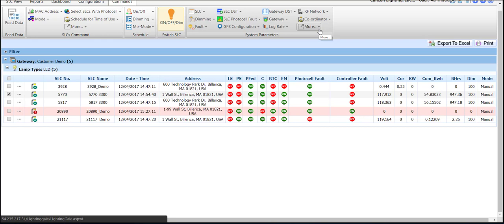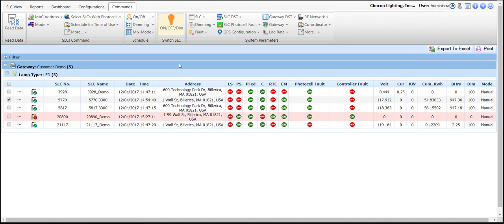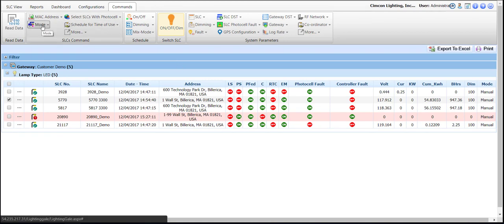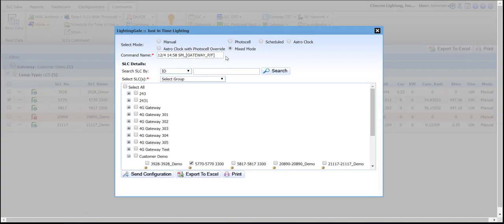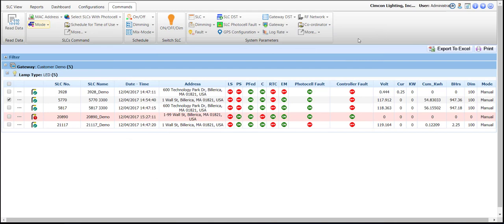Now let's say we have confirmed visually or via the CMS that this SLC is operating as expected and the testing is complete — we will want to revert this SLC back to its previous mode of operation. I will come in here under the Commands tab, then go to Mode Set, and bring it back to mixed mode. I select that, the SLC is selected, and I send configuration. To verify that it has returned to its previous mode of operation, we would want to read data from it to pull the new state into the status screen within the CMS interface.